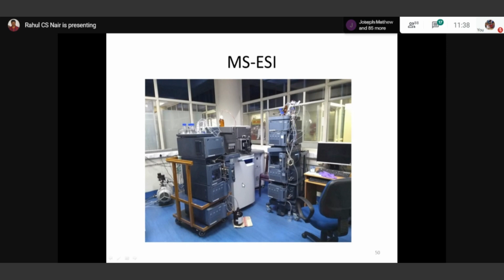This is the setup of our instrumentation system. You can see this white portion, the Waters HD 5000 machine, and this is the injector portion. All the other systems are meant to introduce the sample into the unit, and this is the work surface for that. You need gases like hydrogen, nitrogen and argon at various stages of operation, and these are supplied through proper gas regulators. So this is the entire setup of the mass spectrometer.